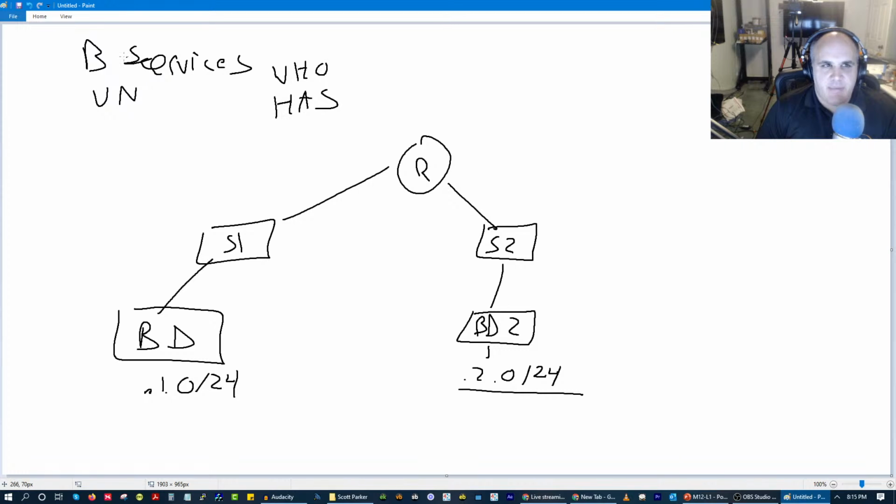So the first thing that happens, when we do a discovery, the BACnet device is going to send out the Who-Is, and it's going to get an I-Am reply. And it's going to build a list of BACnet devices. And those devices are really the IP address plus the device ID.